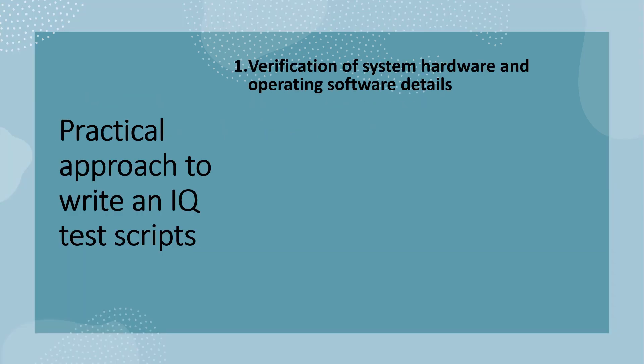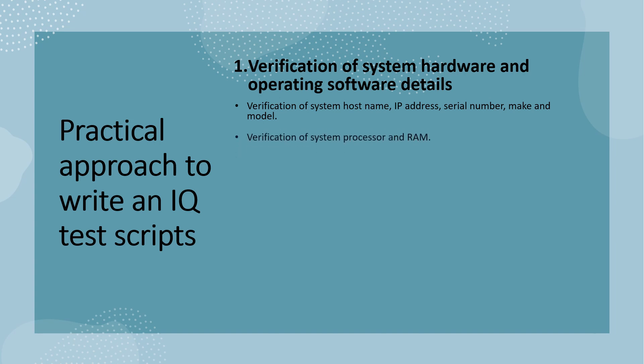Now in this slide, we will discuss the practical approach to write an installation qualification test script. The first test script is for the verification of system hardware and operating software details. In the IQ test script, the following details need to be mentioned for verification, but are not limited to: verification of system host name, system IP address, system serial number, system make and model. Next is verification of system processor and drive capacity.